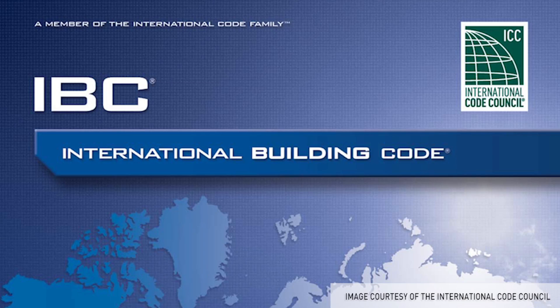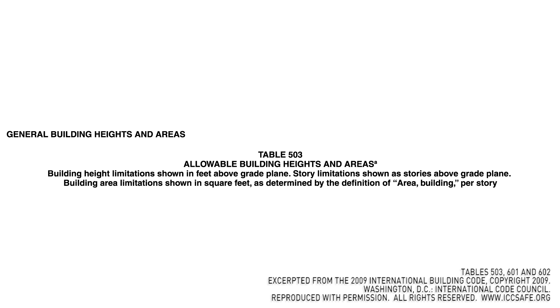The Building Code requires fire resistance ratings for certain types of construction. In the International Building Code, there's a table that provides the basic heights and areas allowed for specific occupancies and specific types of construction — that's Table 503. It gives you the allowable square footage, the baseline allowable square footage, and also the height, number of stories, and how tall you can go.